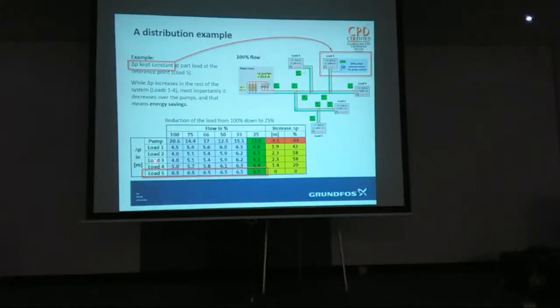So that one there, load 3, where's load 3? 1, 2. That one there is going to see a slight increase in pressure as these ones come down and you reduce the flow. So you're still going to get increases and decreases in pressure, but then your differential bypass valves, or whatever you've got in the system, will compensate for that. So you're not pushing more water down those inadvertently. If you've just got ordinary valves with a hole that big, at 1 bar it'll pass, I don't know, 2 litres a second, at 2 bar it'll pass 4 litres a second. So you need a pressure differential bypass valve, top of range, etc.